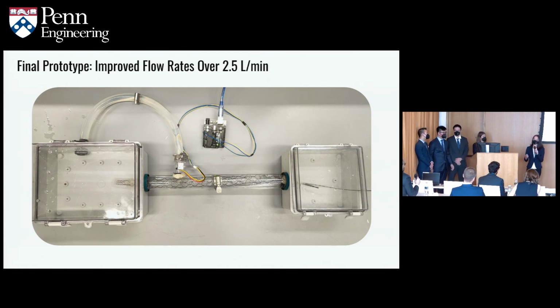Yeah, so compared directly with the Impella, right now the Impella is around 14 French, which is around 4 millimeters, and ours, when it's compressed, can be around 3.3 millimeters in width. So it's almost a millimeter of difference in width, so that would decrease the complication rates. But we'd also have to test that in animals and in humans to validate it. And also, most of our data is through a very loose sheath, so there's a lot of inefficiencies, and even then we're still able to match and exceed the flow rate of the Impella, which is 2.5 liters per minute. And hopefully that answered your question. Yes, it did. Okay.